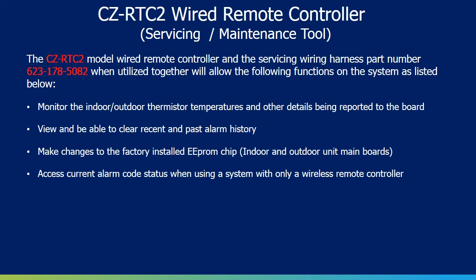The alarm history can also be viewed and cleared from either the indoor or outdoor unit's main control boards. Changes can also be made to the factory programmed EEPROM chip settings. The current active alarm code can be read by plugging into either the indoor or outdoor unit's main control board for troubleshooting purposes.